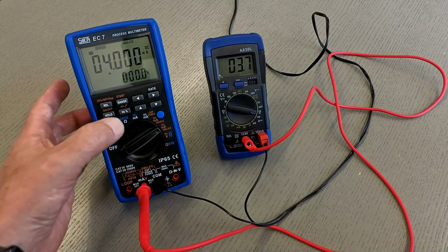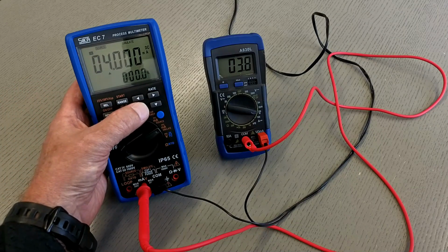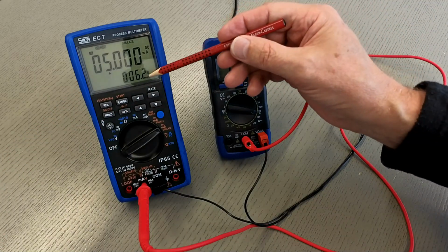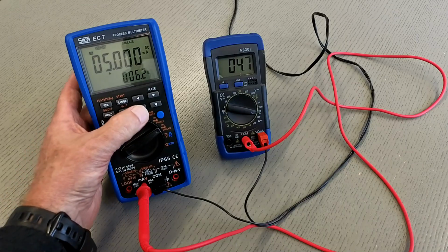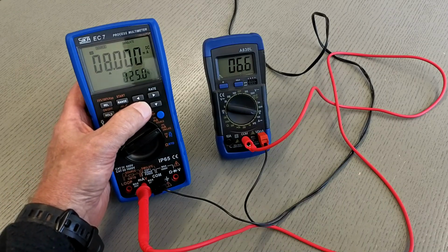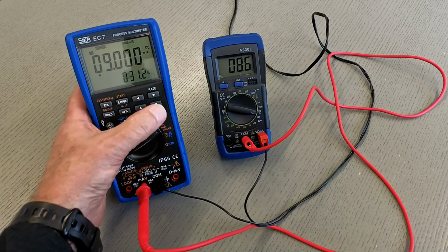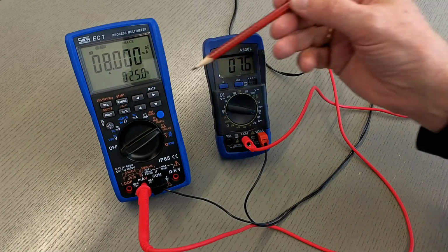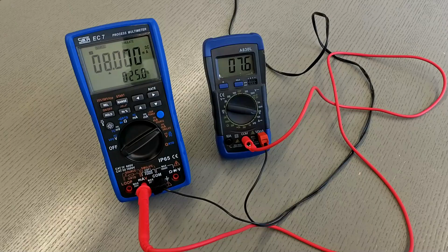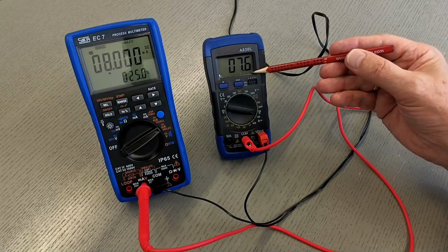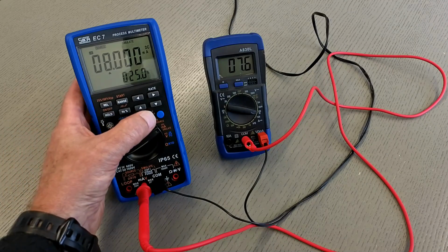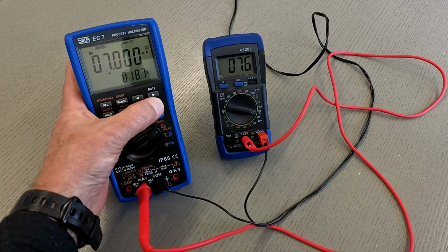And if I'd like to change the value, I can do this very easily. I increase the value, and then I see 6.2%. I increase a little bit higher, for example, to 8 milliamps. So that means 25%. And here I even see the 8 milliamps in the loop.